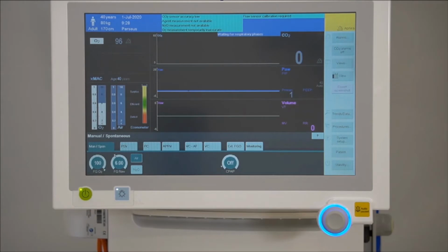The messages regarding gas measurement will appear until the gas bench warms up and is calibrated. This usually takes a few minutes. As you can see, the technical and advisory messages regarding gas measurement have now disappeared off the screen, which indicates the gas bench has warmed up and been calibrated.